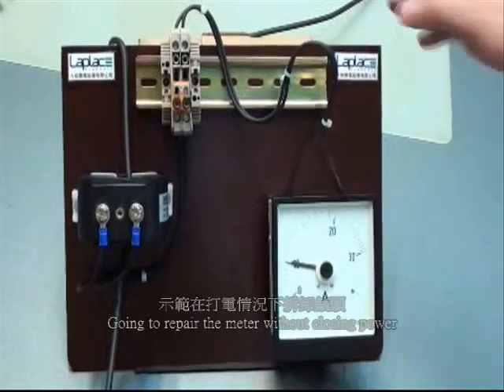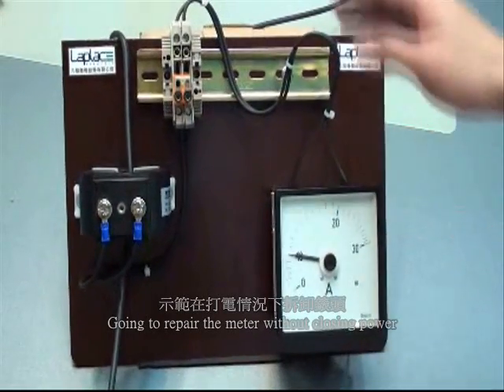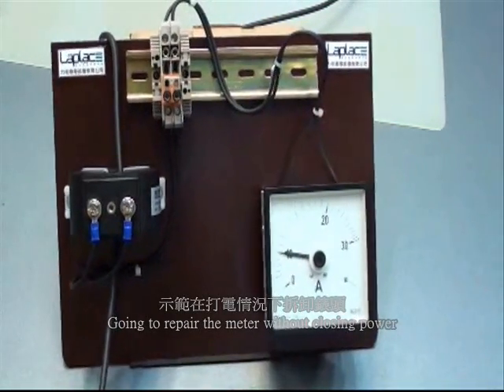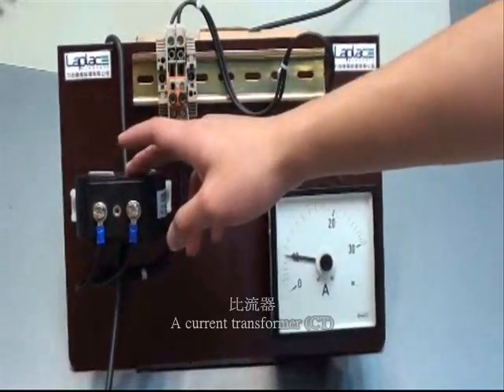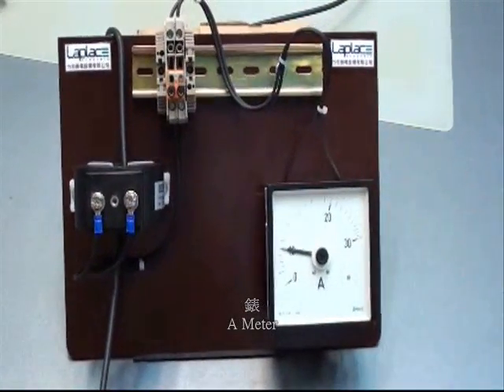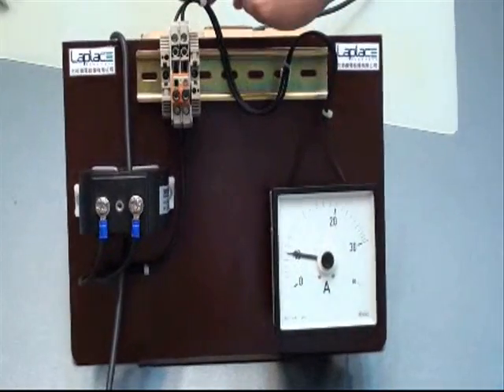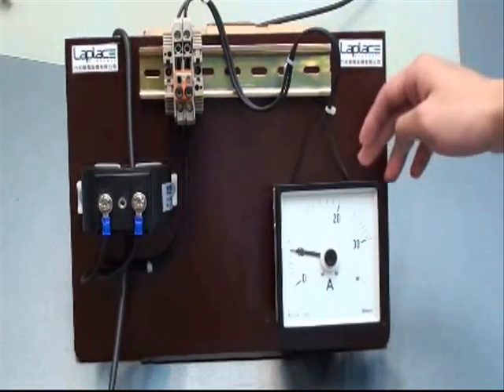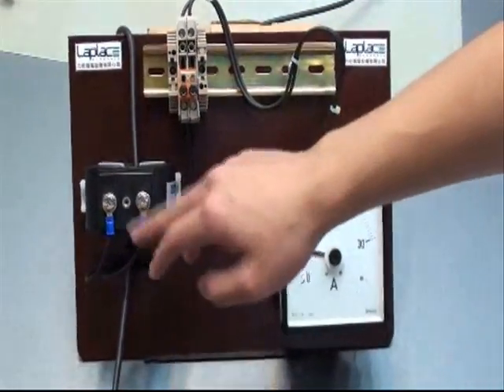And then we are going to demonstrate how to repair the meter without switching off all the electric power. We will have a model with a CT and a meter. The top wires are linked to the meter and the bottom wires are linked to the CT.